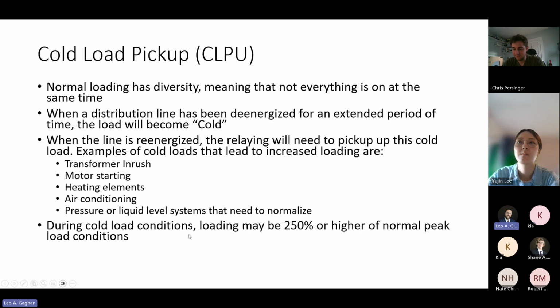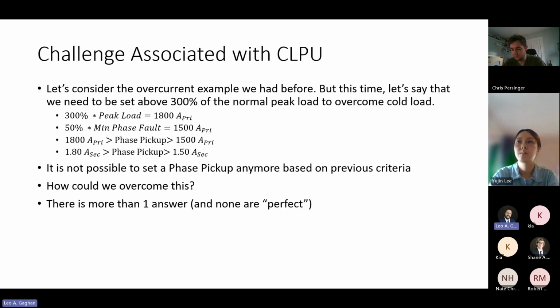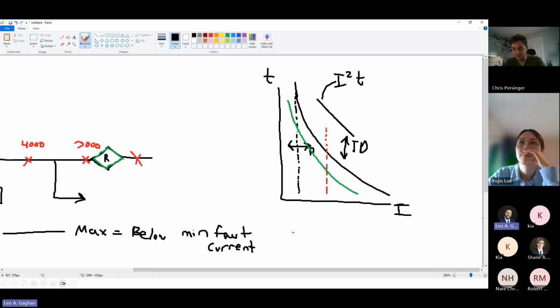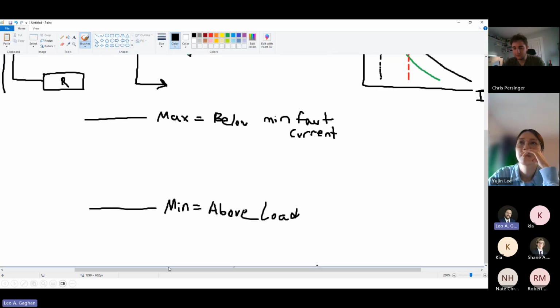So during cold load conditions, loading maybe 250% for example of a normal peak load. The challenges with that, we'll look at it mathematically here, but I think visually it's maybe a little bit easier to work with. So everything that I had been talking about has a minimum setting, which needs to be above load. You've got a maximum setting which needs to be below the minimum fault current. Like I said, everything in this range is acceptable.